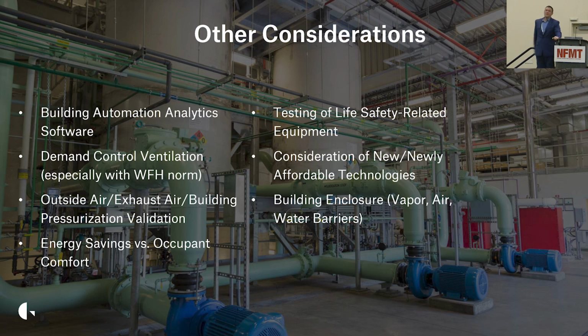Building pressurization is pretty important. You don't know it until you have a negatively pressurized building, and a year or two later you've got moisture and mildew problems, which is a very costly problem to mitigate. So making sure you have a positively pressurized building, more outside air than exhaust air, is pretty important just in the introductory stage of your ongoing commissioning efforts.